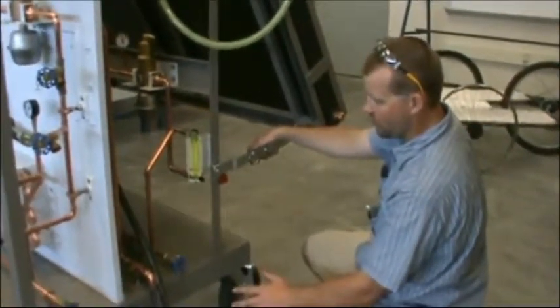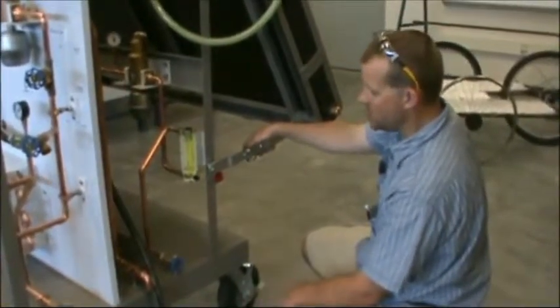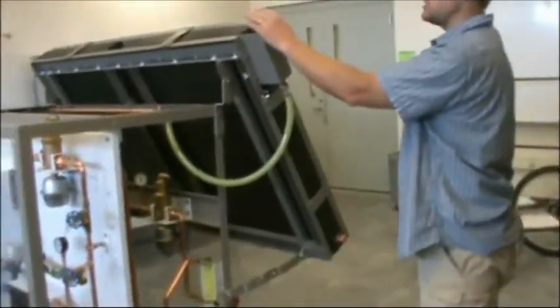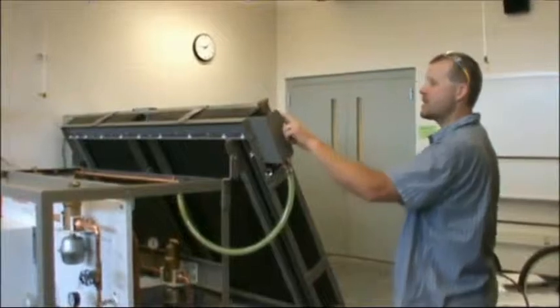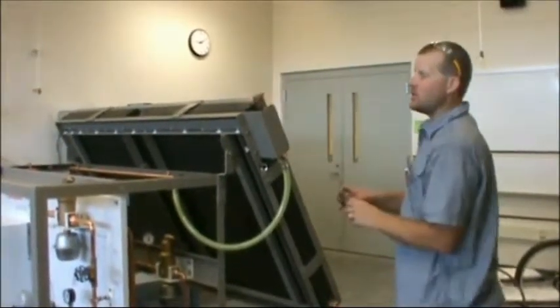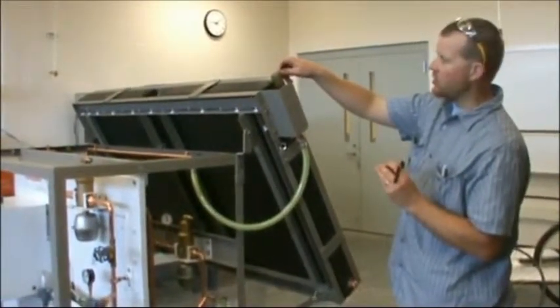There's a couple of processes that you might be able to do. There's different means that other parts do, but one means that you can do is if you come back out to your system and you come up to your cooling air vent, which will be on the highest side, the hot side, and you open this up ever so slightly, you can get this to burp a little bit of air. I hear it burping some air.